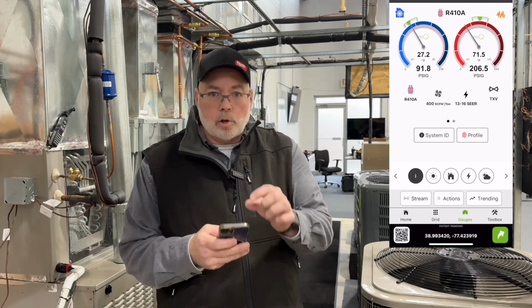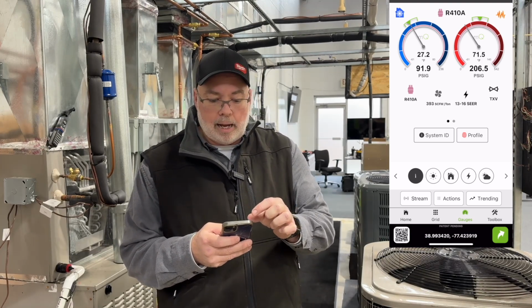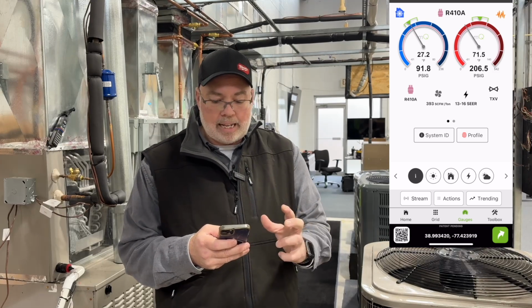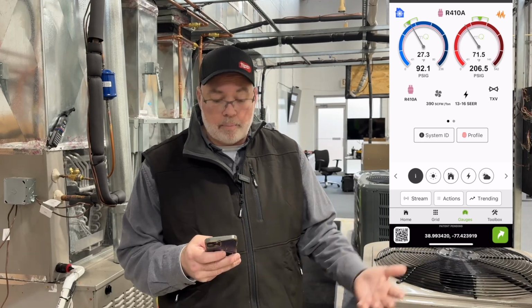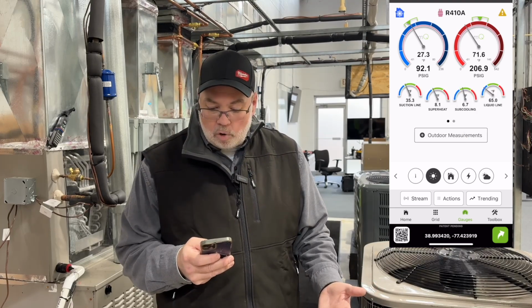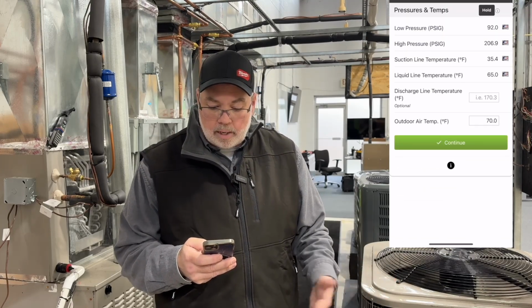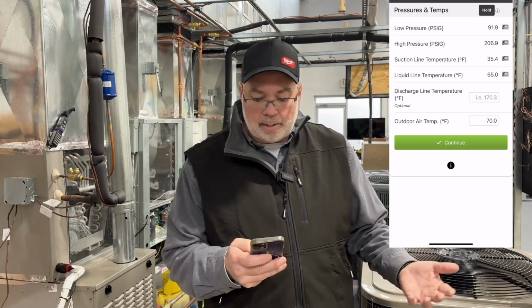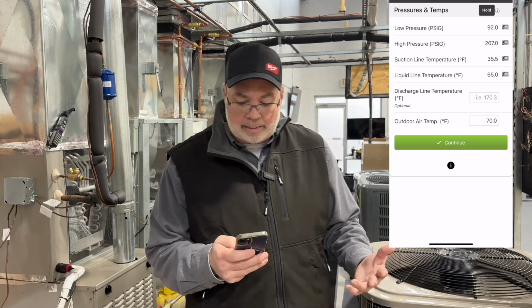Now, we could also go to gauges and see this view here. And the little green bars that you see on both the low and high side gauges, that green bar is where Measure Quick has calculated the pressure should be based on the information that it has. And so when we go to our outdoor measurements, I was messing with it. I plugged in 70 degrees. It's actually more like 60.